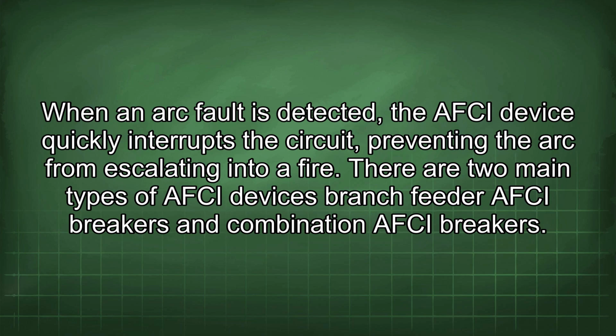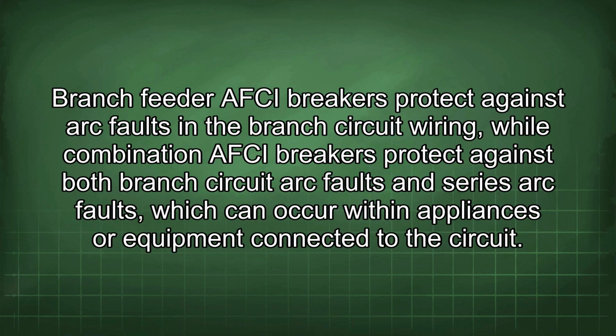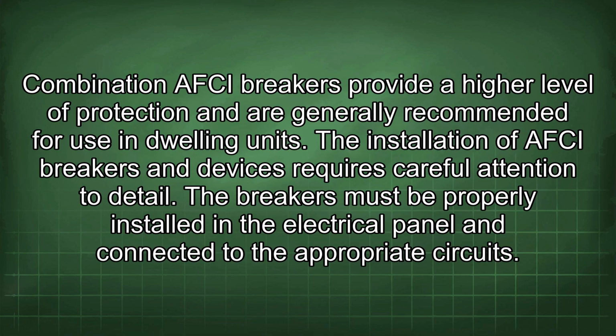There are two main types of AFCI devices: branch feeder AFCI breakers and combination AFCI breakers. Branch feeder AFCI breakers protect against arc faults in the branch circuit wiring, while combination AFCI breakers protect against both branch circuit arc faults and series arc faults, which can occur within appliances or equipment connected to the circuit. Combination AFCI breakers provide a higher level of protection and are generally recommended for use in dwelling units.